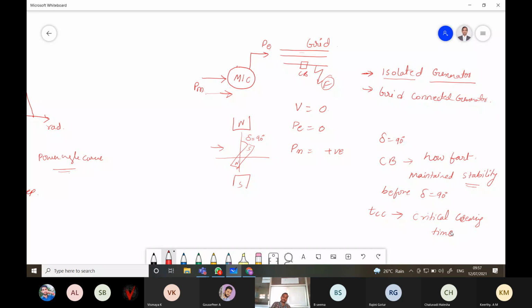Before the critical clearing time, there are a lot of numericals to find out the critical clearing time, that is, how fast the circuit breaker has to operate before clearing the fault. So this analysis will come into this chapter. This is a very interesting chapter, how we achieve stability and all those things. Okay, so this is the thing.